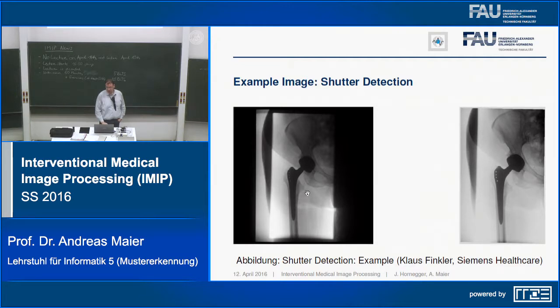Here you can see a combination of the two. You have a shutter that is completely opaque, so here you can't see anything. Then you have an additional shutter moved into here, a kind of wedge filter. Typically, these complete shutters have something like 2 millimeters of lead, which is enough to block the direct X-ray beam completely, so there's no illumination past it. Then you have those aluminum wedge filters that you can use to additionally control the image.